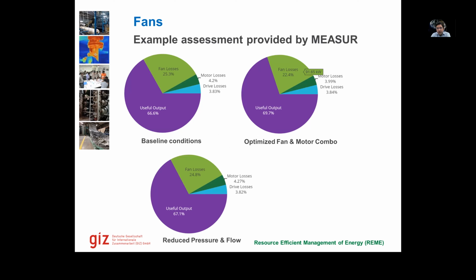An example assessment done in MEASUR had a baseline condition where the usable output provided by the fan was 66.6%. For a scenario where they optimized the fan and motor combination, the useful output increased and fan losses reduced. And when they reduced the pressure and flow, the useful output was still better than that of the baseline conditions, and fan losses were also lower than the baseline conditions. So this is the kind of assessment you can also do directly in MEASUR. I highly recommend using MEASUR for the next audits that you do.